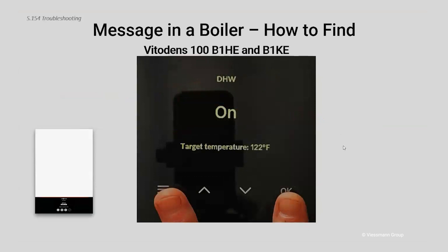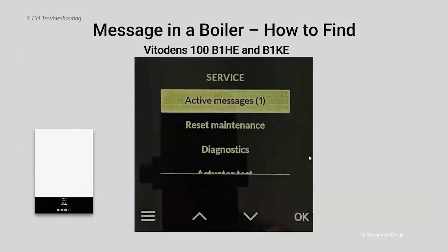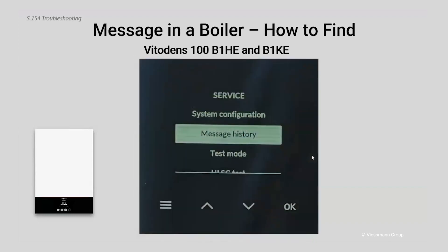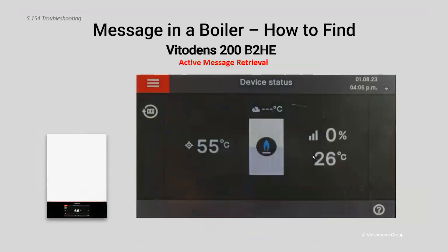The second way to navigate through the 100 boilers is to make a 'V' with your fingers — or a peace sign — and put them across the OK and menu keys, holding both buttons down. After a few seconds the screen will flip to the service screen. If you see 'active message' highlighted at the very top, that means there's an active message currently on the boiler that needs to be addressed. Hit OK to see what that message is, or scroll down to message history to view archived messages.